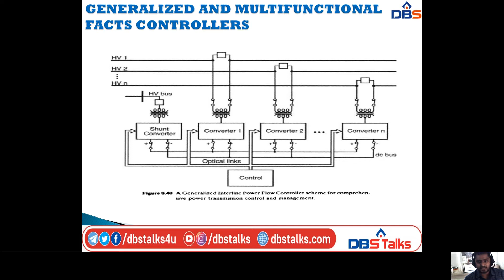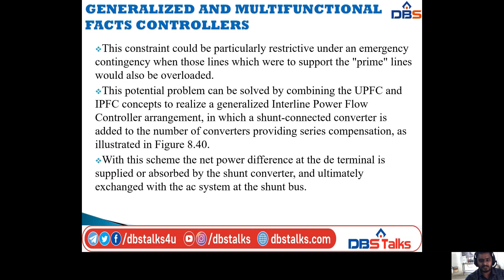With this scheme, the net power difference at the DC terminal is supplied or absorbed by the shunt converter and ultimately exchanged with the AC system at the shunt bus. This arrangement can be economically attractive because the shunt converter has to be rated only for the maximum real power difference anticipated for the whole system.